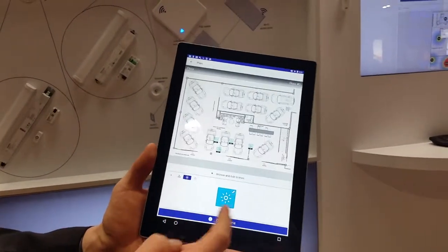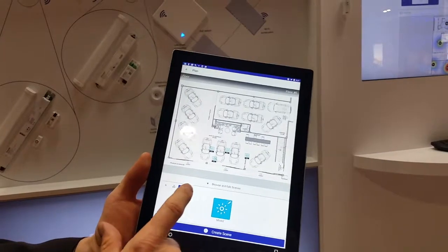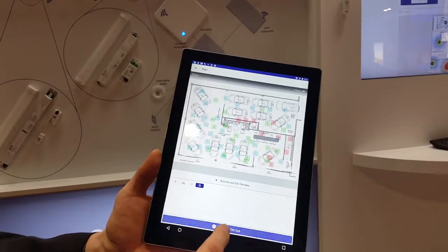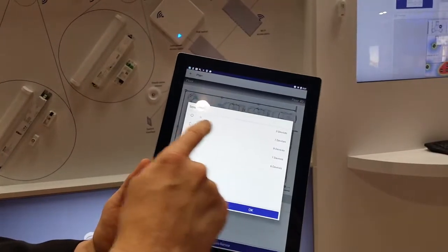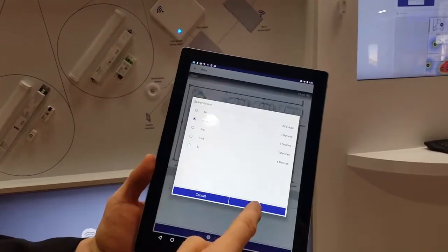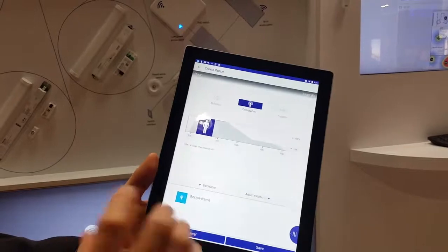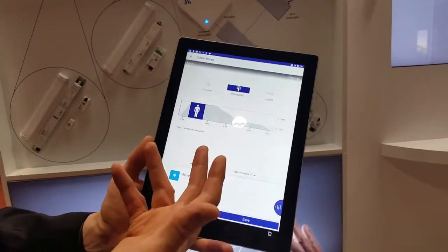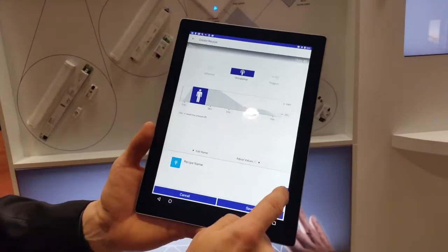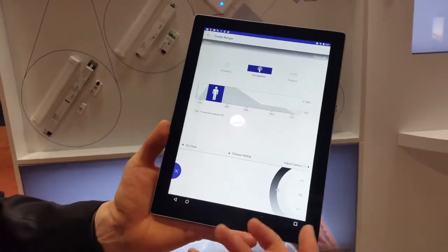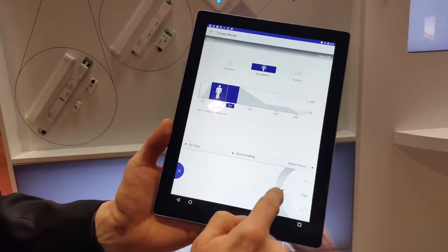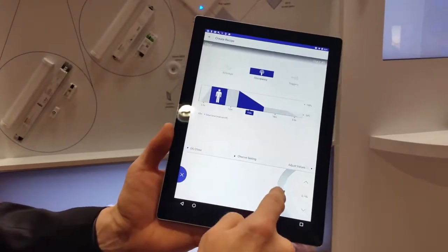And last but not least, if you have a group with a motion sensor, you can go in to create a recipe. And a recipe, let's select this main group here that has a motion sensor in it. And depending on what's in the group, you will see the contextual information. Like here, in this case, we have a motion sensor, so this interface looks familiar to a DALI commissioner, where you can basically select all the values and change your timeout, fade out times, and max values and so on.